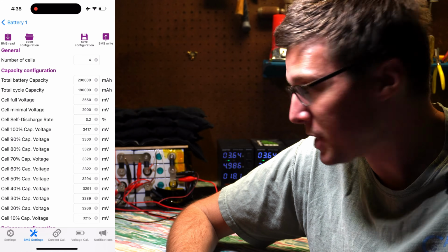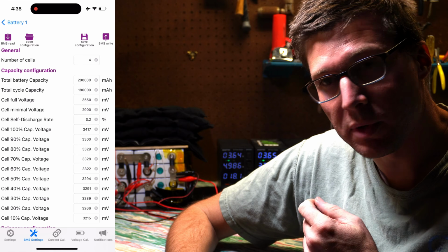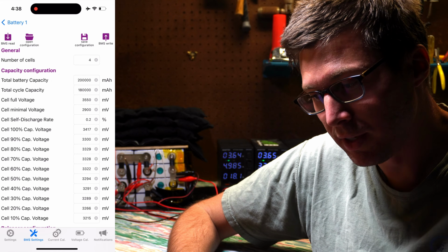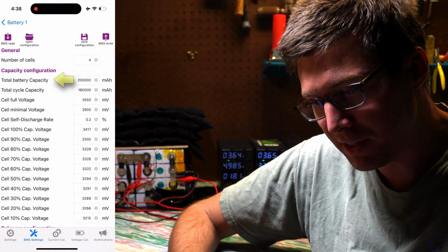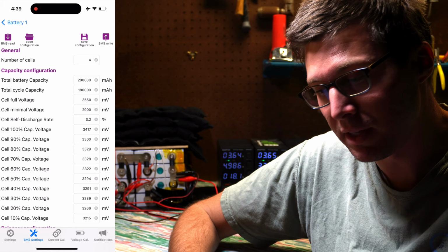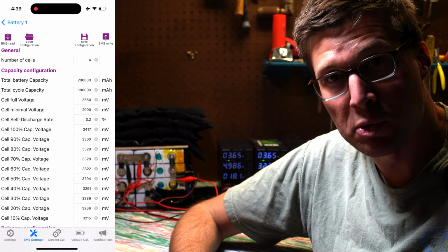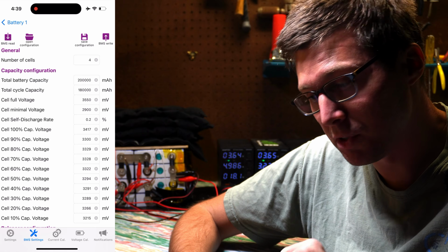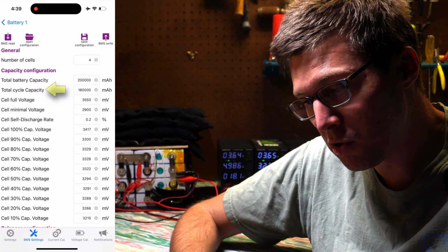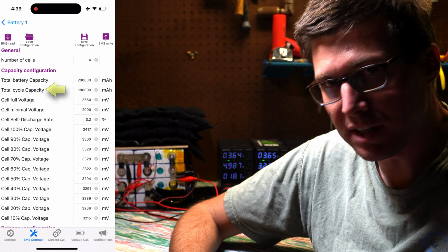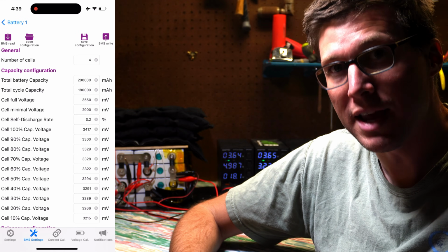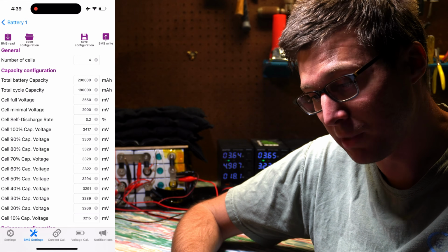So in this situation, they're 100 amp hour cells, so we have 200 amp hours total. Now, the total battery capacity is in milliamp hours, so that means add 1,000 — so you have 200 amp hours, add 3 more zeros behind it. Now the total cycle capacity, I have it set conservatively: we have 180,000 milliamp hours available.